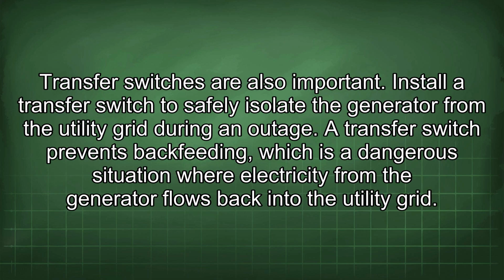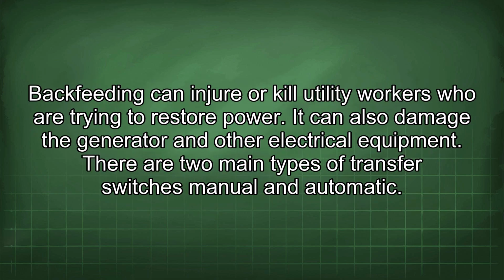Transfer switches are also important. Install a transfer switch to safely isolate the generator from the utility grid during an outage. A transfer switch prevents backfeeding, which is a dangerous situation where electricity from the generator flows back into the utility grid. Backfeeding can injure or kill utility workers who are trying to restore power. It can also damage the generator and other electrical equipment.